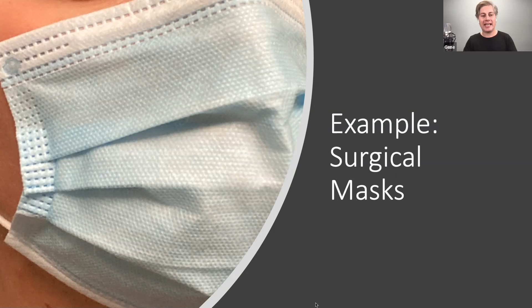But the default roadmap that a company these days thinks they have, especially if they went through the emergency use authorization process, is that they need to do biocomp testing, fluid resistance testing, filtration testing, flammability testing, and maybe pressure testing. They need to submit that to the FDA, and they're going to get their 510K. At least that's the impression that many companies have. We've had a lot of conversations where people are saying, oh, I just need to do this testing and I need to submit it to FDA and then I'll have a 510K.